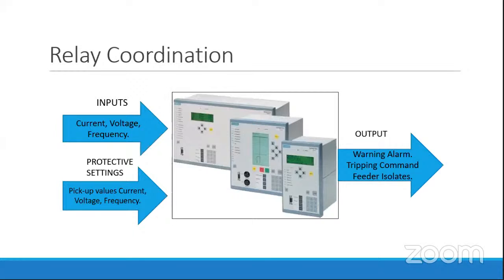The relay coordination. The term relay means the automatic device which senses an abnormal condition in the electrical system and gives a tripping command or a signal to the circuit breakers associated with this relay. The protective relays have functions like measuring current, voltage, frequency and temperature, and with these measurements it gives the tripping command to the circuit breaker.